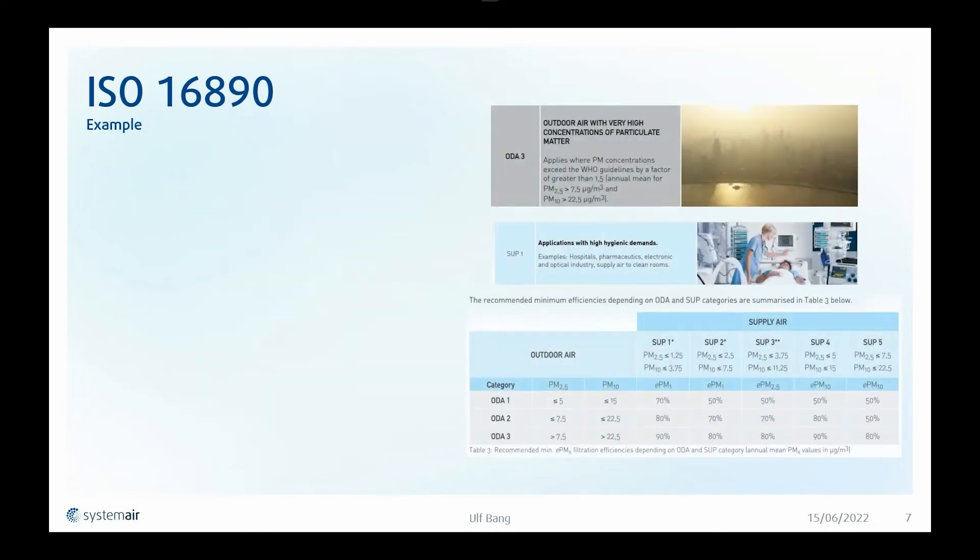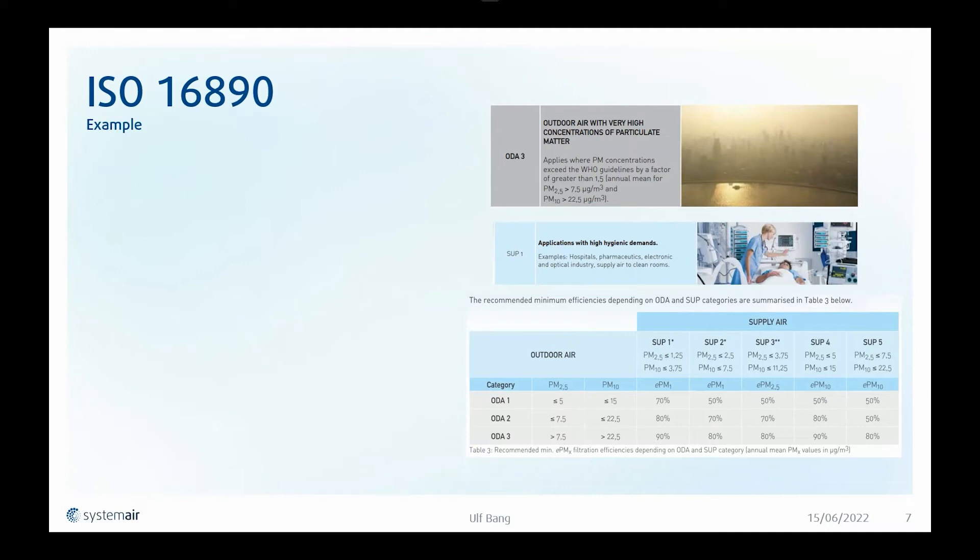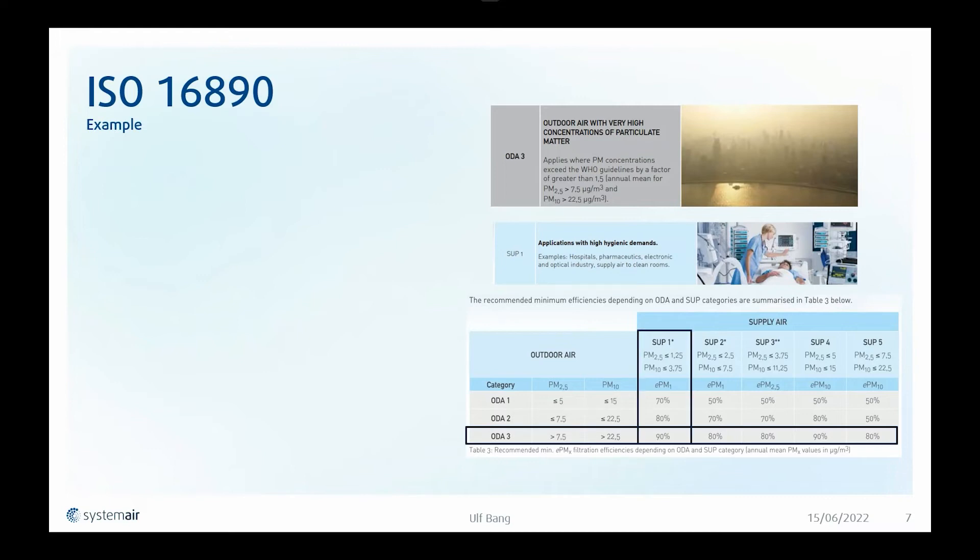Let's take an example. We have outdoor air 3, we are in the city at a hospital, so we have high hygienic demands, so it is a SUP 1. And if we check the reference table, then we can see that ODA 3 SOP 1 will require an EPM 1 90% filtration.